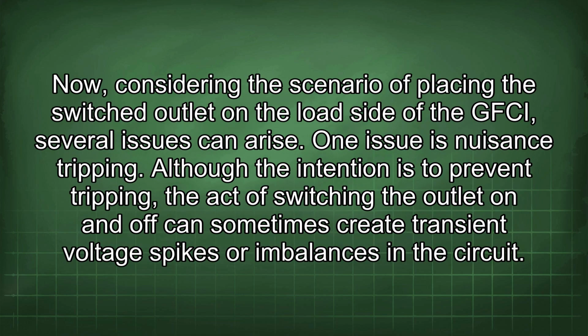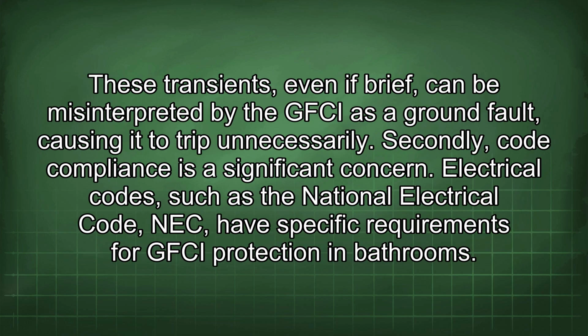Now, considering the scenario of placing the switched outlet on the load side of the GFCI, several issues can arise. One issue is nuisance tripping. Although the intention is to prevent tripping, the act of switching the outlet on and off can sometimes create transient voltage spikes or imbalances in the circuit. These transients, even if brief, can be misinterpreted by the GFCI as a ground fault, causing it to trip unnecessarily.